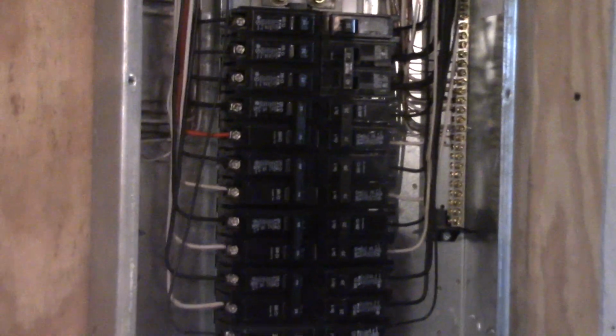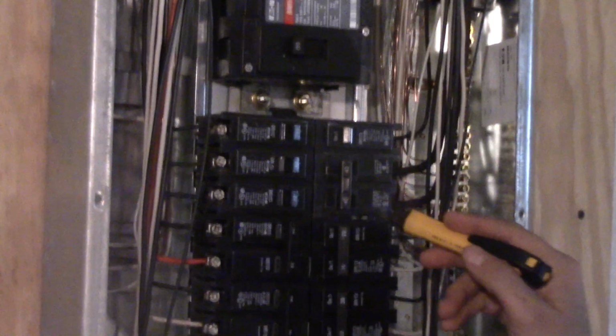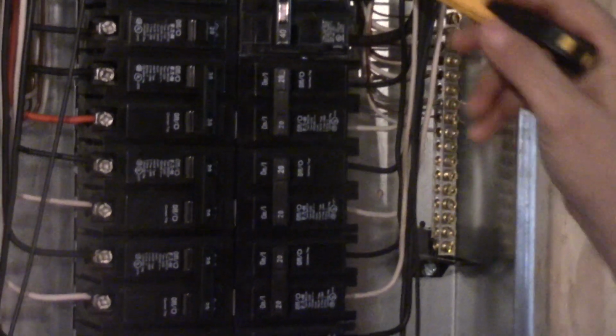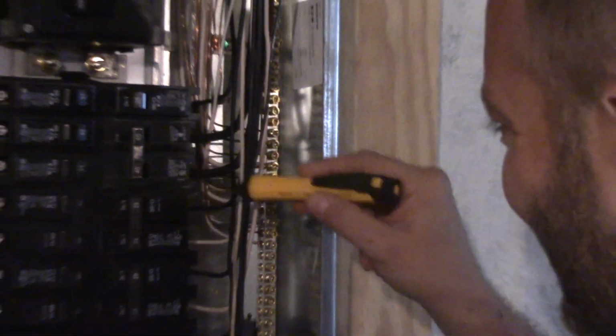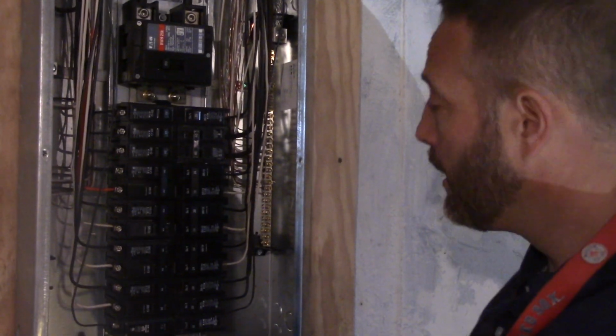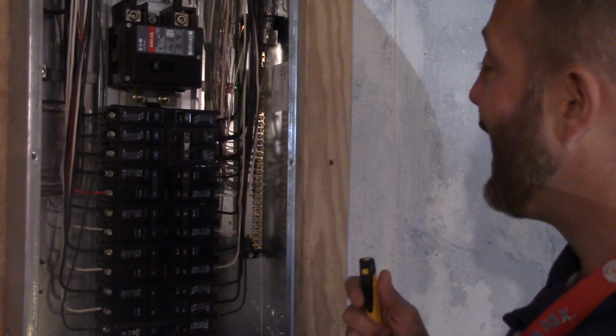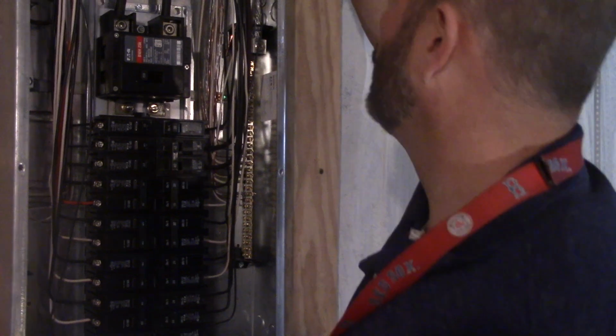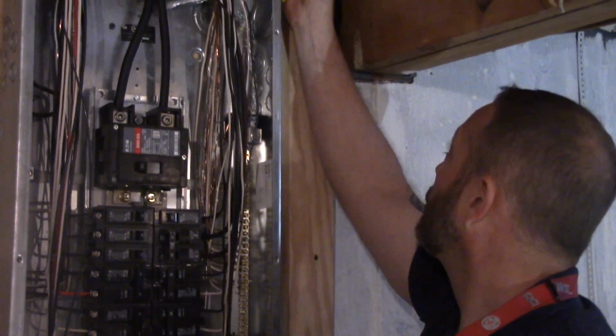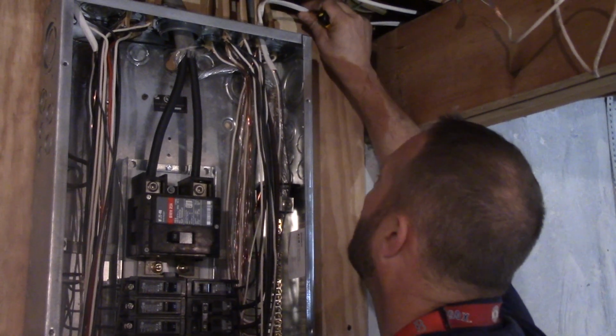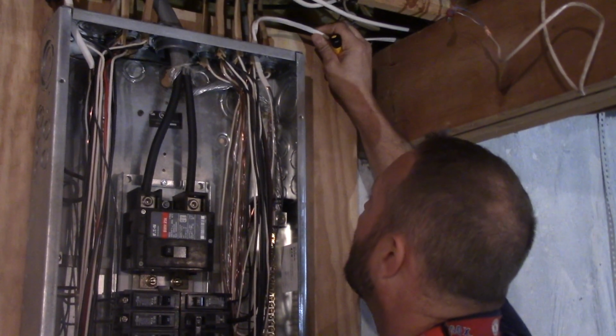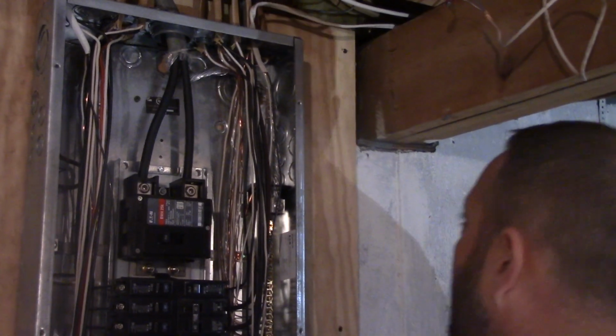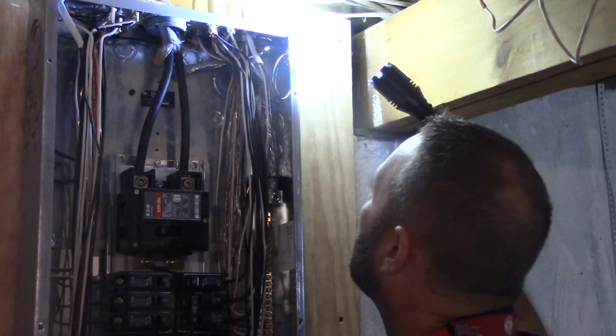So this is where we're going to begin looking at each individual breaker and see if the corresponding wire is appropriate for the size. So here we have a 20 amp breaker. Now, it may be difficult to actually say to yourself, so what size is that? If you don't have any reference wires, maybe you get at Home Depot or Lowe's, what you would end up doing is look at a wire and then you're going to look at the sheathing itself. So if we look over here, and sometimes you got to pull out your flashlight to look along the side, and this is one way to do it. Is it a little bit more difficult? Yep. All right, so that is 12 gauge.